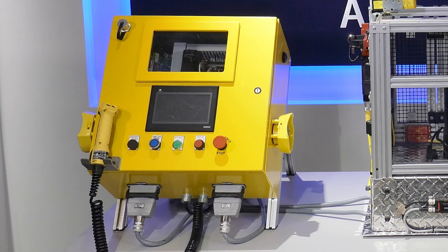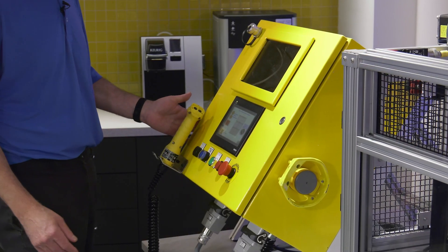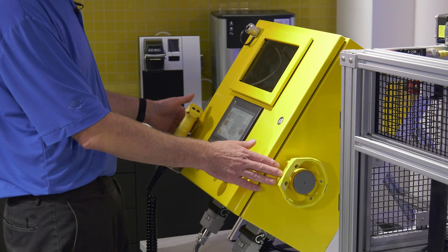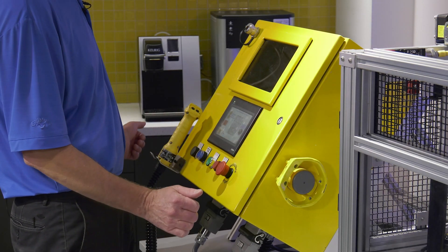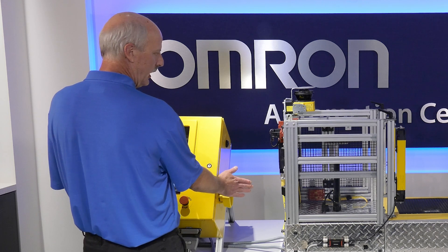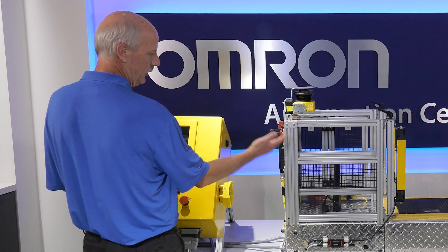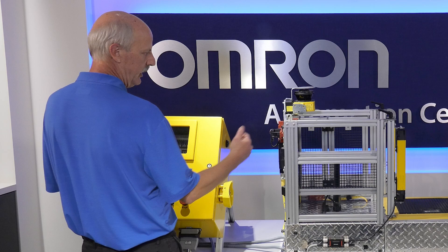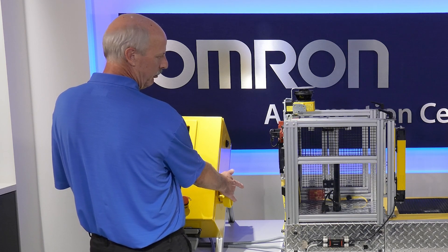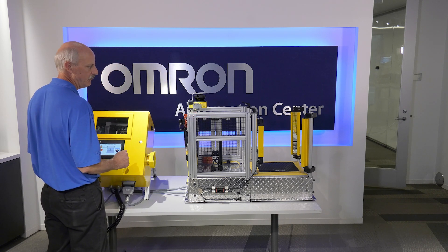The next item is our two-hand control. On each side of the enclosure there is a capacitive-type push button — no pressing force is required, just your hand getting close enough. These are tied to a door: if I actuate them and release too soon, it stops the machine. If I hold them in until the complete movement of the door, the machine keeps running. Having the two switches prevents me from putting my hand into the pinch point area when operating.